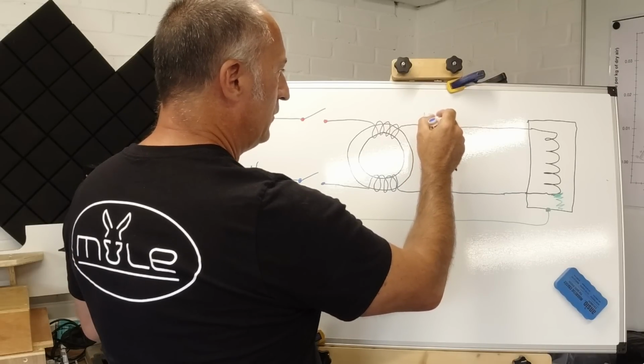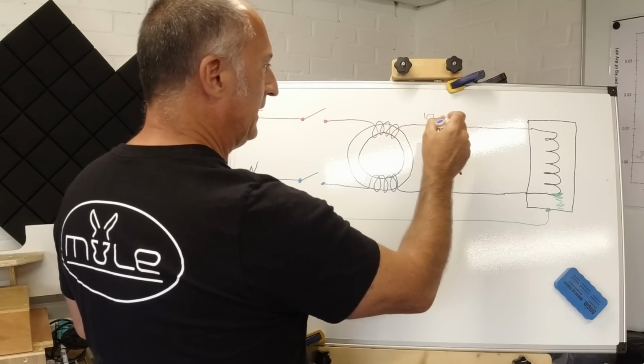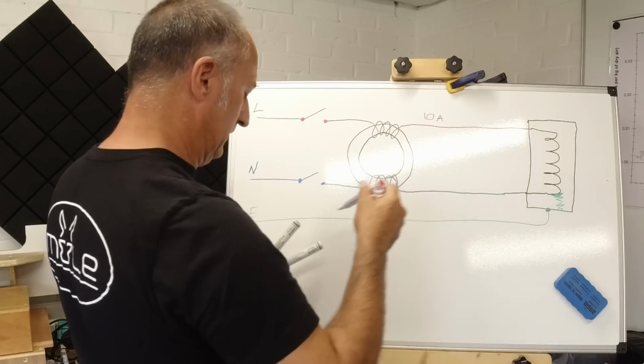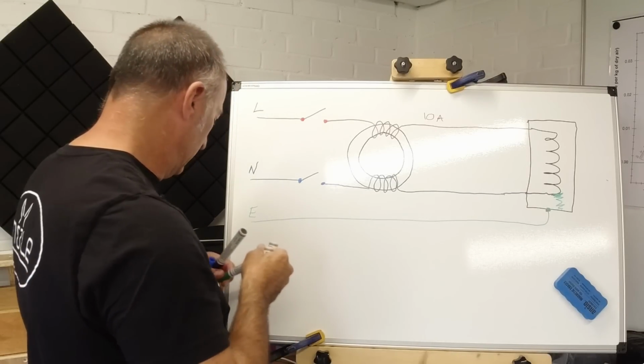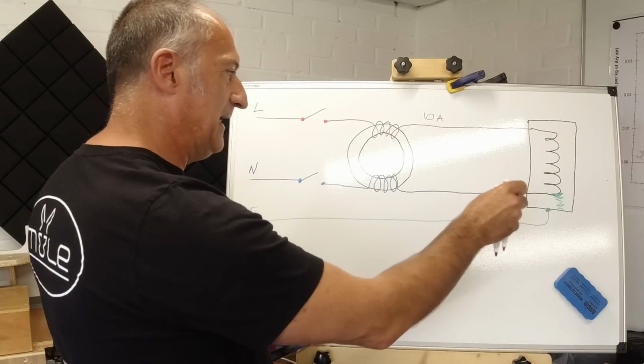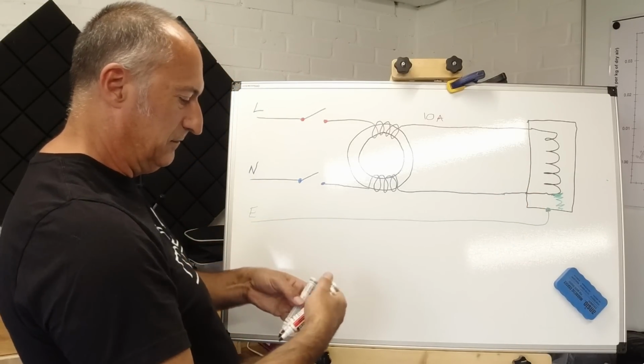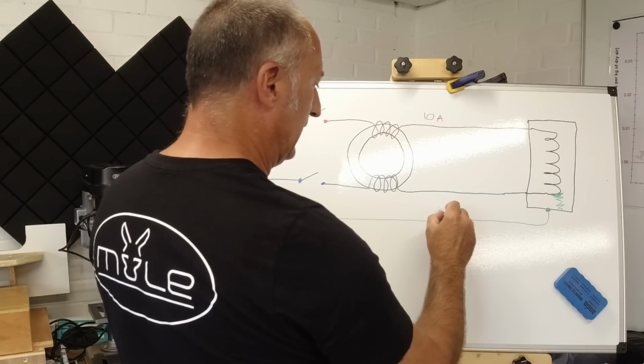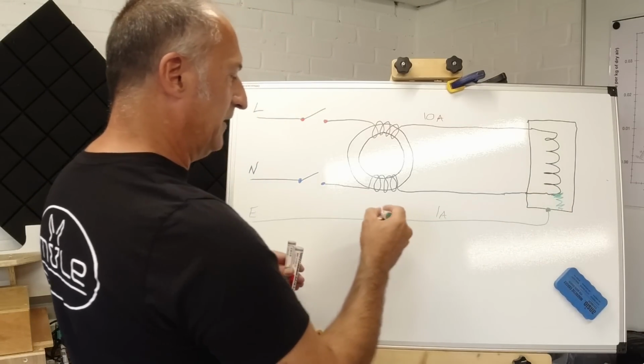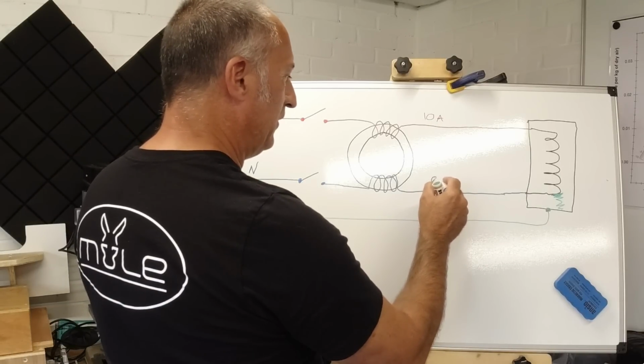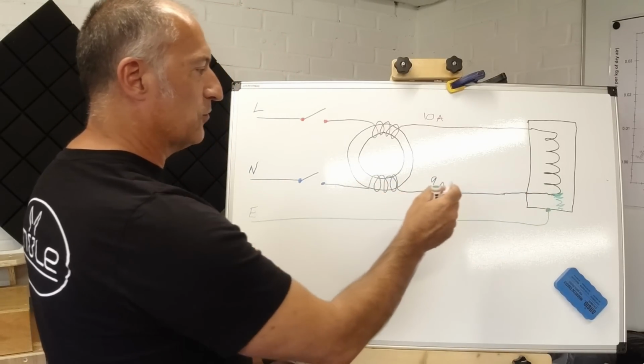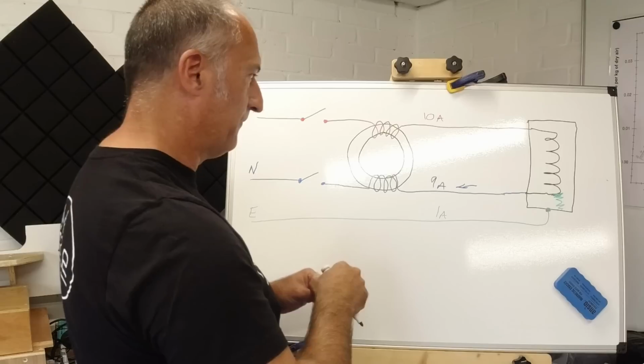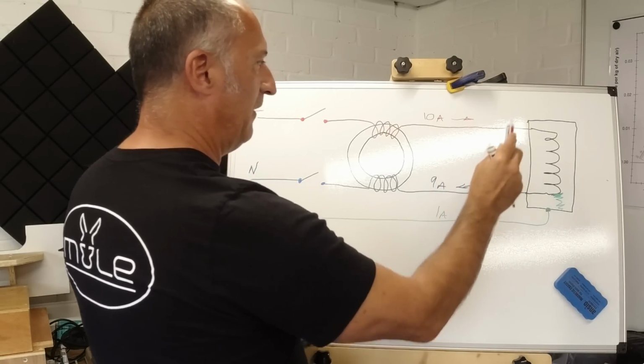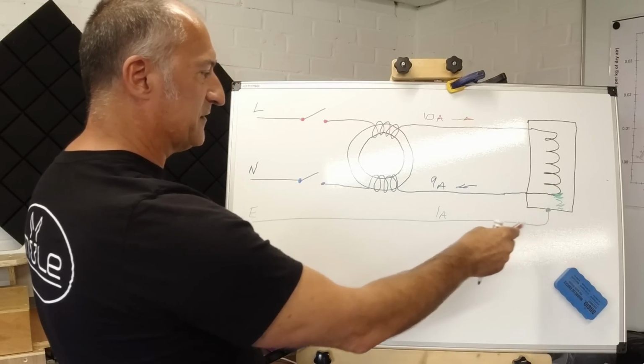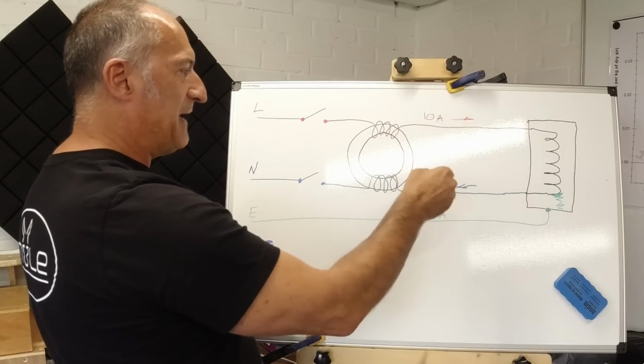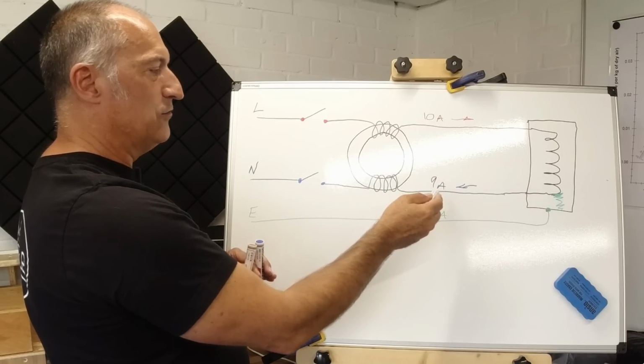So let's say we could have something like 10 amps flowing down the line to this device, but some of the current is leaking out to earth. For argument's sake, let's just say we had 1 amp leaking out along the earth, so we're only going to have 9 amps coming back on the neutral line. 10 amps going to the appliance, we've got our fault, some of it's coming back on the earth, so there's an imbalance across the line and neutral.